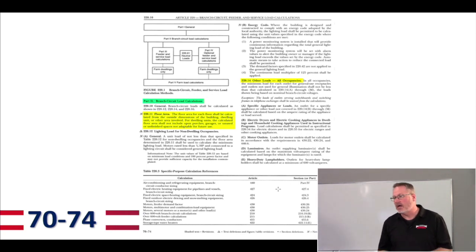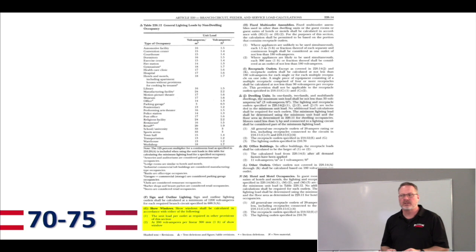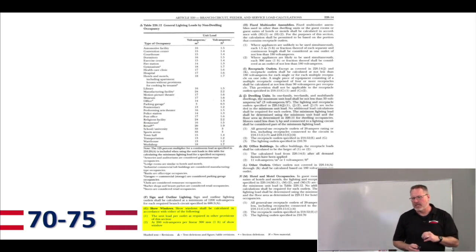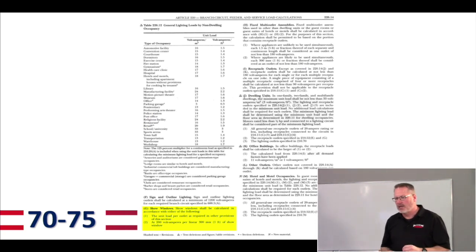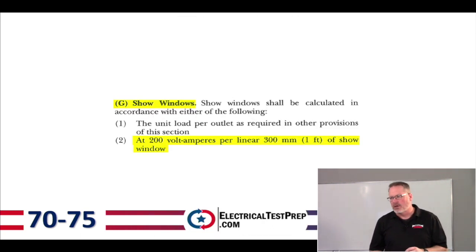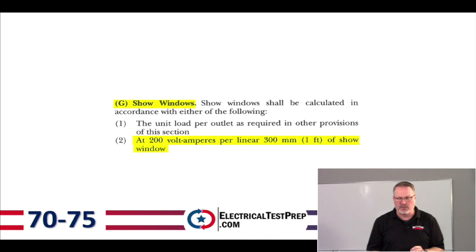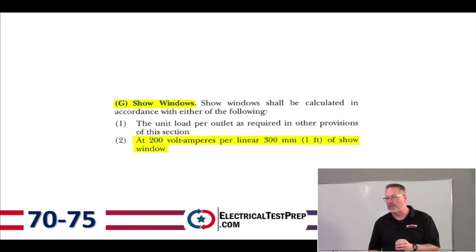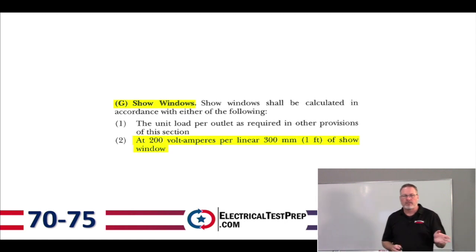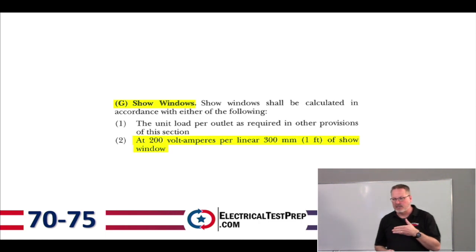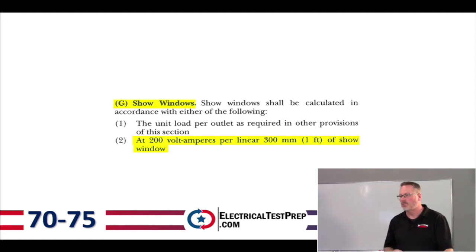On page 74, middle of the right-hand column, we've got 220.14, Other Loads, All Occupancies. Under letter G, Show Windows — there will be a question on the exam about show windows. The load is 200 volt-amps per linear foot of show window. For a 20-foot show window: 20 × 200 = 4,000 volt-amps.